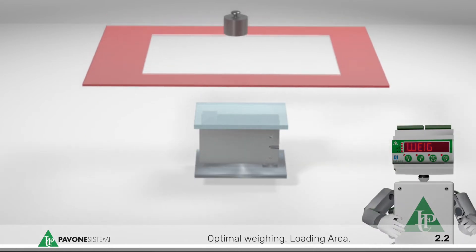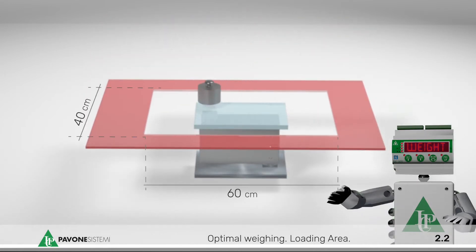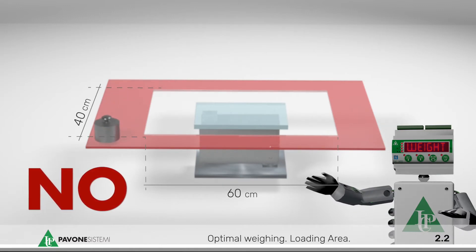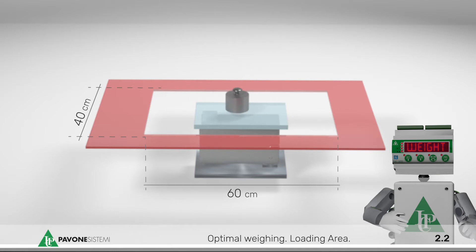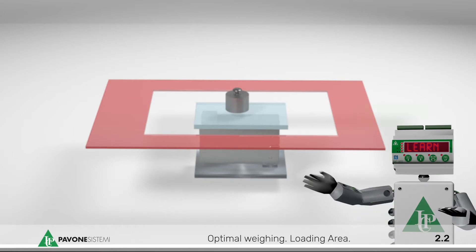the detection will be correct. By installing a structure with a larger size than the depth set on the datasheet or by applying an object that protrudes from the structure, it is possible to damage the off-center load cell and, in any case, obtain an incorrect weight value.